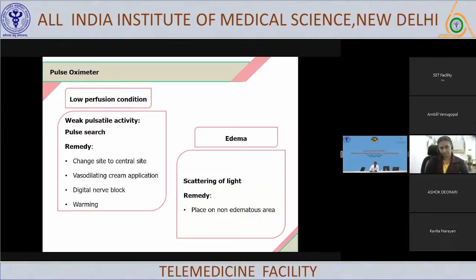Low perfusion, especially when they have hemodynamic issues. In the hospital setting, some pulse oximeters have technology that can pick up low perfusion. But in those situations, when you're using the finger probe, they may show a wrong reading. So you can change to a central site, or you can apply some vasodilating cream or a digital nerve block. We do it. And probably the most common remedy is warming the patient, warming the finger. You can just apply a cotton pad over it. It will warm up and show a good reading.